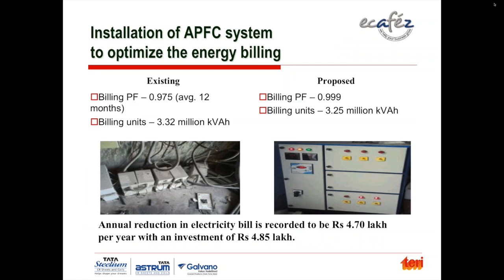Now, another example of saving energy is an automatic power factor correction system. For some units, particularly in UP, the billing is based on kVAh, not on kWh. So there the power factor becomes very important and critical. As you can see, earlier the billing power factor was 0.975, a 12-month average, and the amount of energy units billed was 3.32 million kVAh.